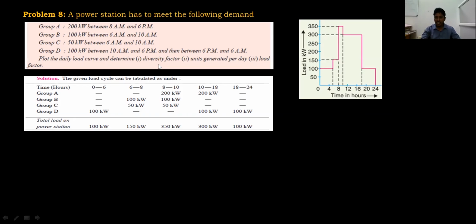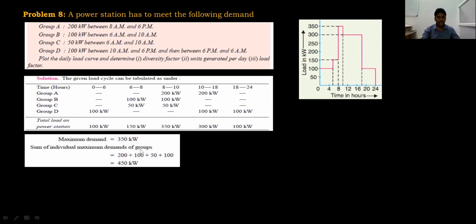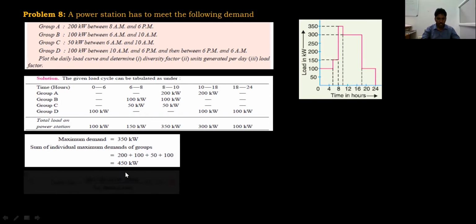So the only thing remaining is the diversity factor. What is diversity factor? It is the sum of individual maximum demands divided by the maximum demand. Say there are four consumers whose maximum demands are 200 kilowatts, 100 kilowatts, 50 kilowatts, and 100 kilowatts. These are the maximum demands of the individual customers. So the sum of individual maximum demands is 200 plus 100 plus 50 plus 100, divided by the maximum demand, 350, which gives you the diversity factor. The maximum demand is 350 kilowatts, and the sum of individual maximum demands of the groups, 200, 100, 50, and 100, gives you 450 kilowatts.